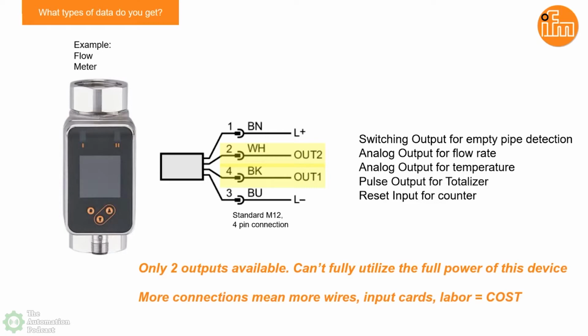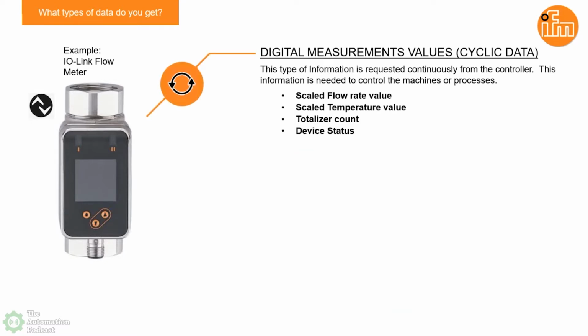So if we take the same flow meter and simply use the IOLink portion of it, we can now get the true digital measurement values. We typically refer to this in the IOLink world as the cyclic data, because this is the type of information you need to continuously get in the controller to control your machine and processes. In this case, we're going to give you the actual flow rate value, the temperature value, the actual totalizer count, and device status information. These are all coming back to the PLC as the actual value, not a 4 to 20 milliamp signal of any form, and you're able to get all this at the same time.